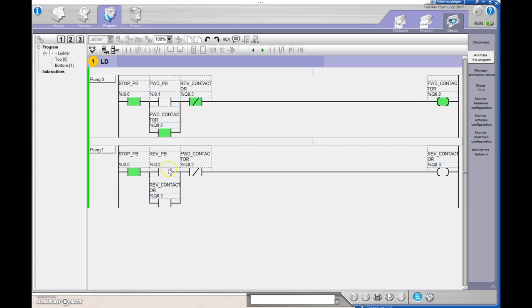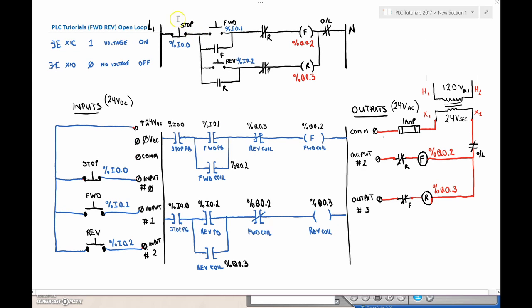If I hit the forward push button, you can hear the contactor turn on. When I let go, you can see that as soon as it turned on, it's being held with another path of logic — this is looking to see that the contactor's output bit is a one, and it's true, providing another path of logic to keep the forward contactor on. If I try the reverse push button, it's coming in but with a bit of lag — it mimics the same behavior as a normal forward-reverse contactor in that you have to hit stop to go in the opposite direction.